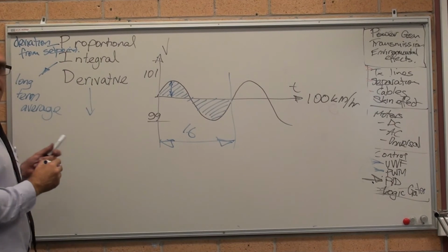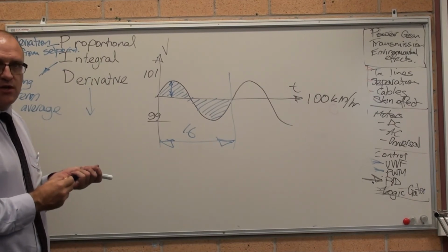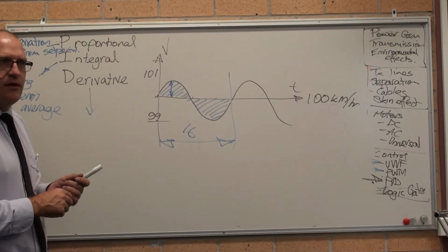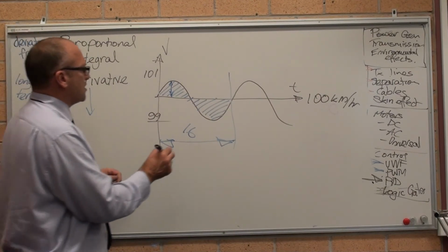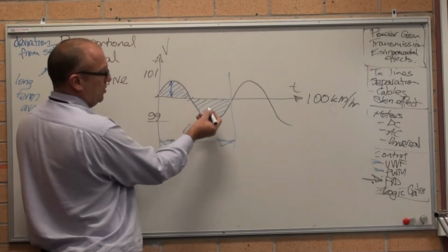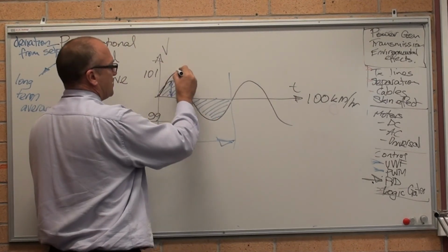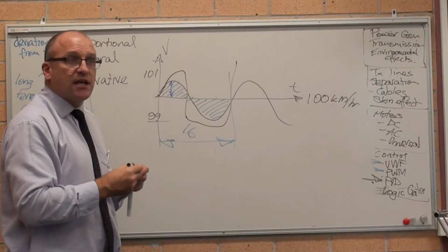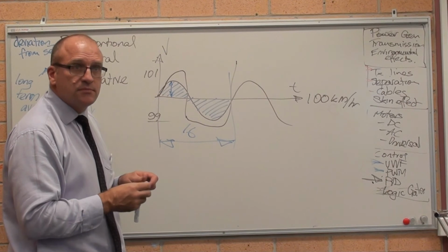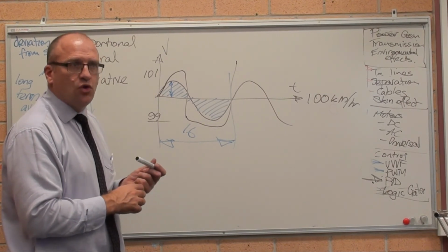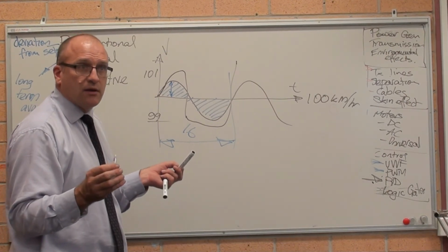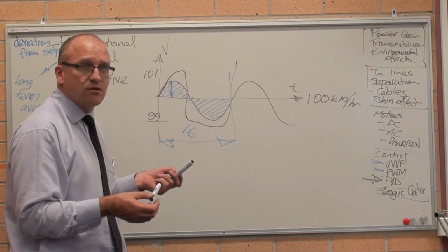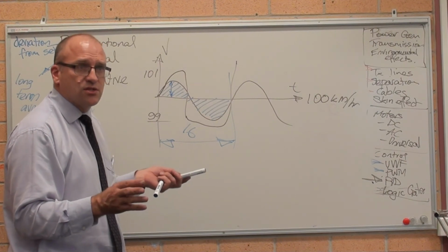And derivative, point blank, you set it to 0 in industry and you don't worry about it unless you really have to. The derivative is how steep that slope is. If the reaction's like that, do something, if you've got a sudden sharp reaction in the system. Highly unlikely. Normally it's set to 0 and you don't worry about it. It's probably 0.5% of your control scenarios in industry where you've got to use derivative. Other than that it sits on 0.